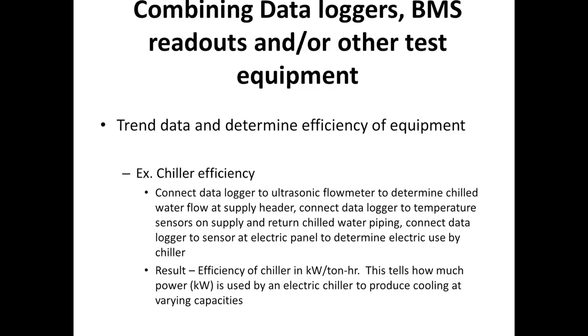One important example that I want to express to you guys is that we can get creative with logging data, combining it with single point measurements and also using other equipment. To look at things like chiller efficiency, we can install an ultrasonic flow meter on the chill water supply pipe, so we actually know how much water flow is going through the pipe. Looking at also the temperature of that water and the temperature of the return chill water, we know how much heat energy or cooling energy is being shed in the building. And also monitoring electricity at the electric panel, we know we can evaluate the efficiency of the chiller at different conditions.